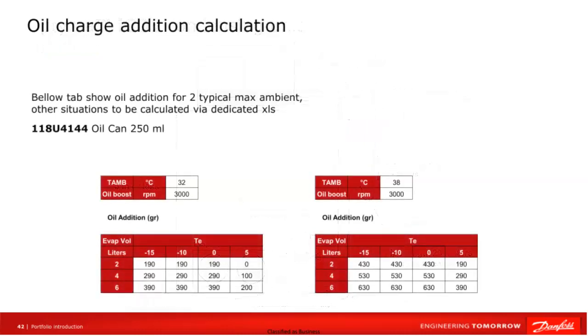This slide highlights an important aspect related to the amount of oil required depending on the specific situation. We present two different situations taking into account a maximum ambient temperature of 32 and 38 degrees Celsius. There is a noticeable difference in the amount of oil that may be needed depending on the conditions. Here we can see the catalog number for a can of oil, 250 milliliters. However, it's worth noting that the amount of oil may change depending on temperature conditions.